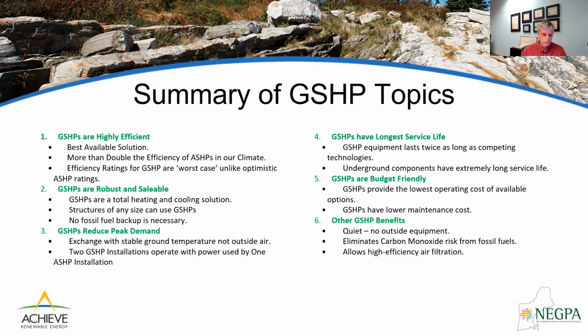But nonetheless, in an actual operational scenario, ground source uses quite a bit less electricity to achieve the same amount of heating and cooling. Ground source heat pumps are robust and scalable — the number of ground source heat pumps you install and their capacity can be varied, as can the size of the ground heat exchanger. So essentially any size building can be addressed with ground source heat pumps. However, the most efficient systems are those where the loads for the building have been reduced to the greatest degree practical. And ground source heat pumps are a complete heating and cooling solution with no requirement for a fossil fuel backup.